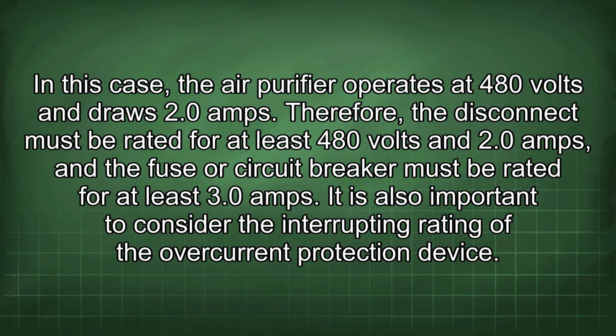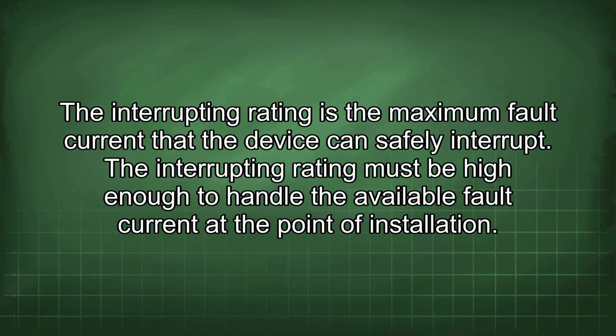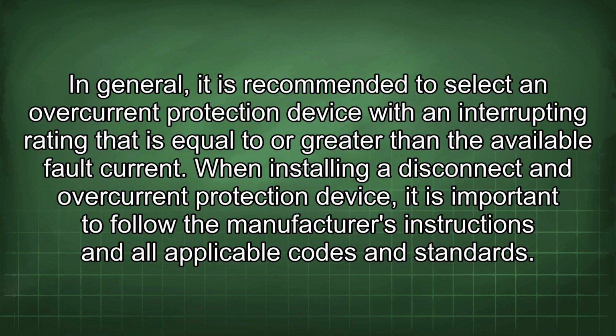It is also important to consider the interrupting rating of the overcurrent protection device. The interrupting rating is the maximum fault current that the device can safely interrupt. The interrupting rating must be high enough to handle the available fault current at the point of installation. In general, it is recommended to select an overcurrent protection device with an interrupting rating that is equal to or greater than the available fault current.